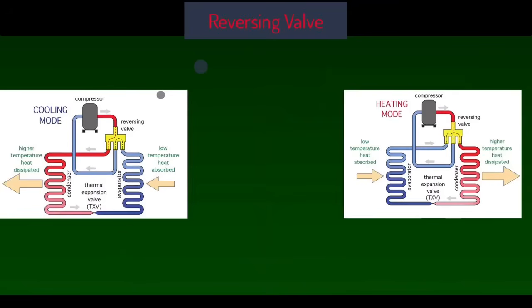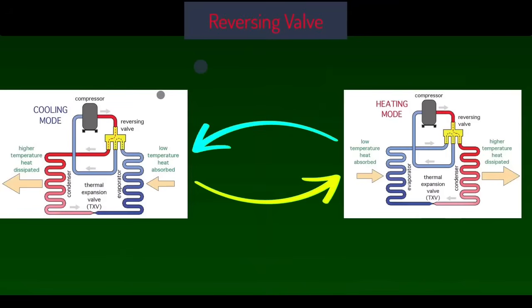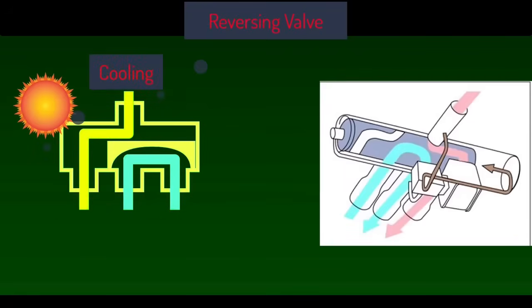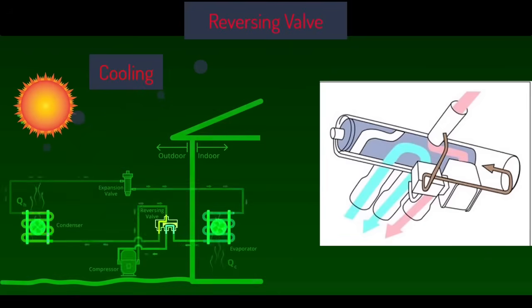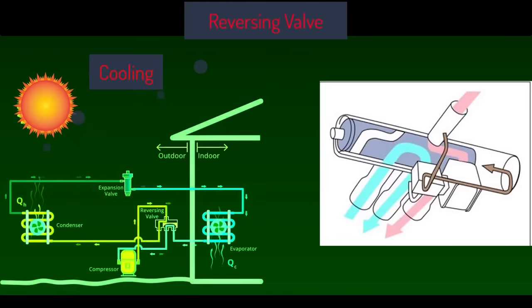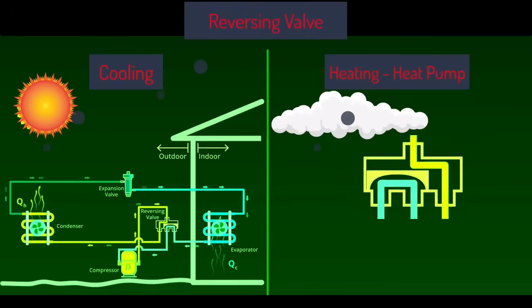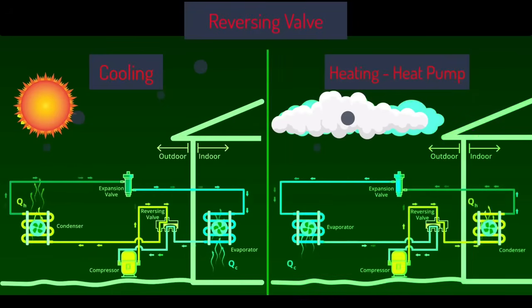Most modern systems can switch between the cooling mode and heat pump mode, but how do they do that? The answer is with the reversing valve, the four-way valve installed near the compressor. In cooling mode, it directs hot and high-pressure refrigerant from the compressor to the outdoor coil, turning it into a condenser. In heating mode, it reroutes the flow so that the indoor coil becomes the condenser and the outdoor coil becomes the evaporator. This single component allows the system to flip its function with the push of the thermostat setting.